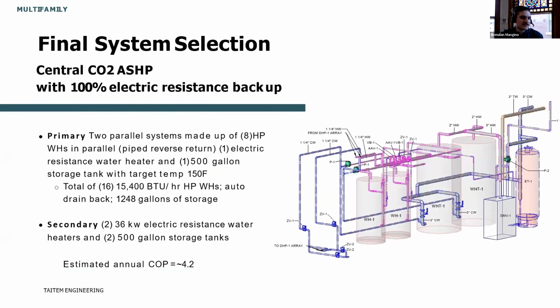So this is the final system selection. We have 2 parallel systems, 8 heat pumps on each side, total of 16 heat pumps, 1 electric resistance water heater on each side, and 1 500-gallon storage tank with a target temperature of 150 degrees Fahrenheit. That 150 was used to increase the effective capacity of the system a little bit more. And then secondarily, we have the 2 36 kilowatt electric resistance water heaters that are housed within those 500-gallon tanks.